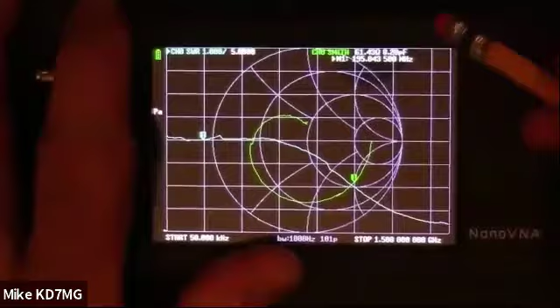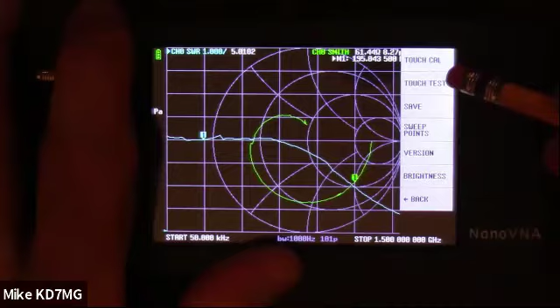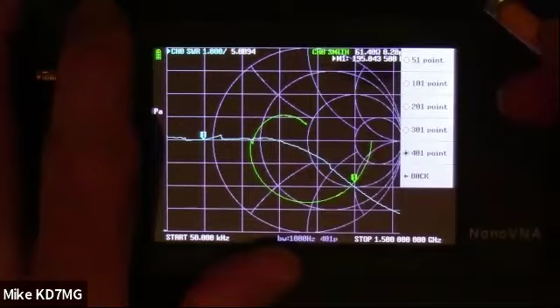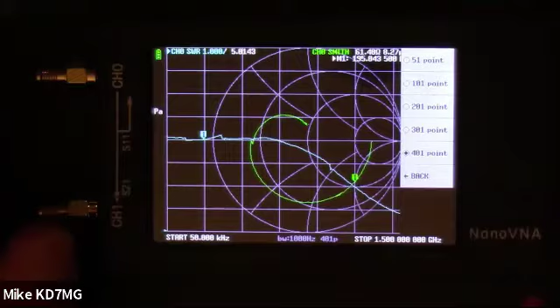Now, a couple other things. Let's go into config. With this last upgrade that I got of the firmware, they added some really cool things. One of them is number of sweep points. It normally was fixed at 101 points across the screen. Now I can select 401 points across the screen. The disadvantage is you get 4 times the sweep time, but the advantage is you get a whole lot more resolution on every screen.